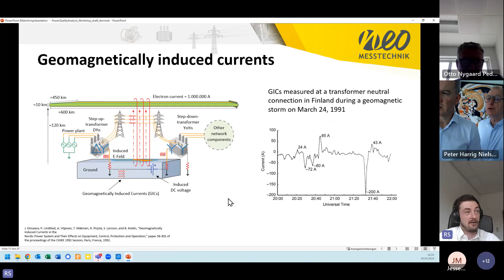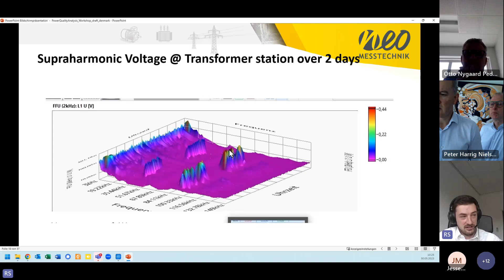So this is something we need to be aware of. We also have DC parts in our grid, and we measured, for example, the voltage at the transformer station over two days. Here you see the higher frequency component, approximately at 80 kilohertz, measured at the photovoltaic part. Over the day we see some power generation, and therefore we see the emission at the transformer station, the higher frequency component. At night, of course, there's no emission, but then on the second day we see this again.